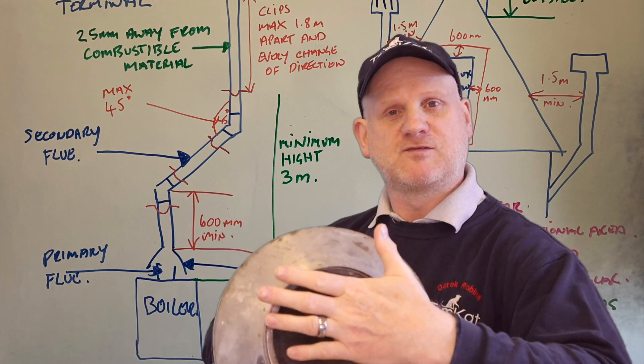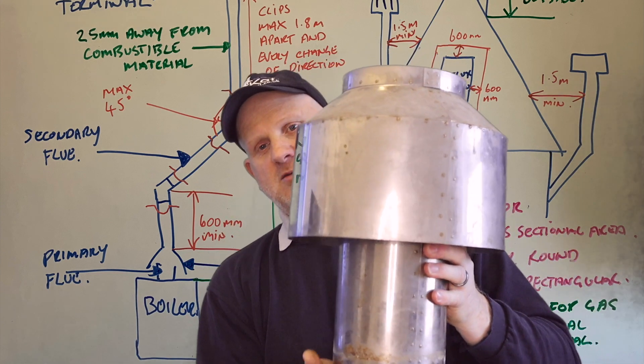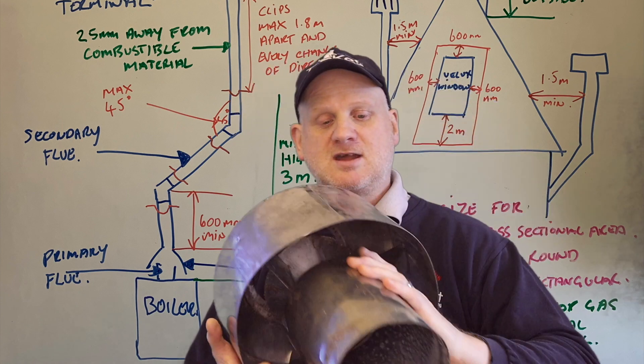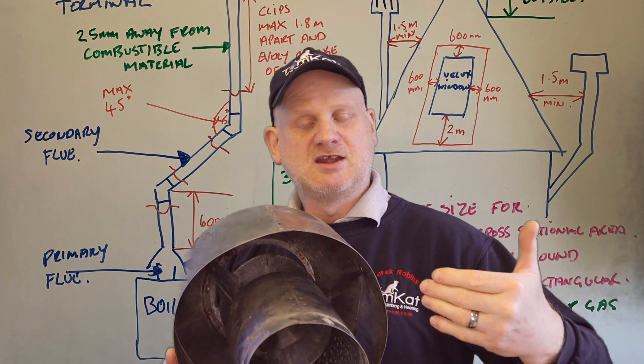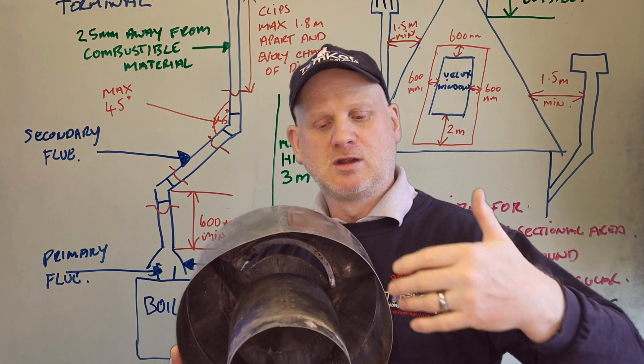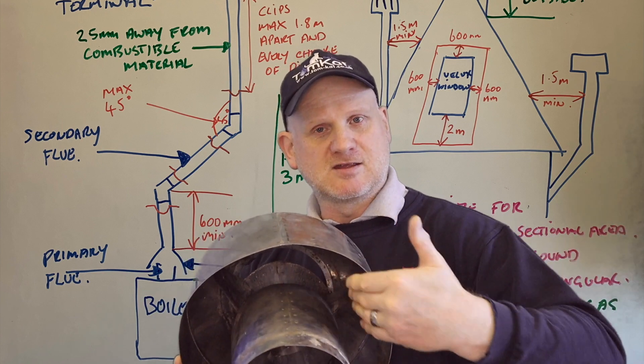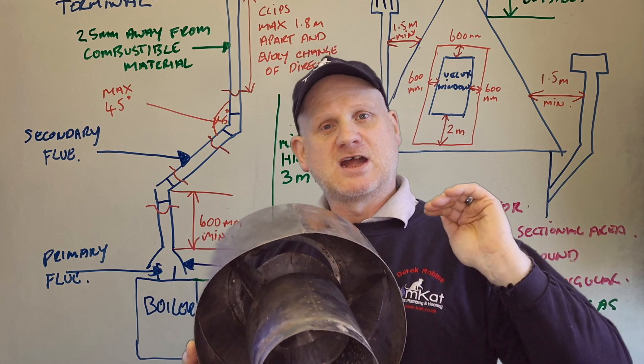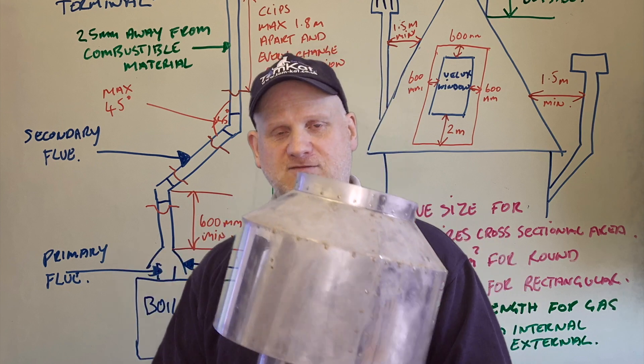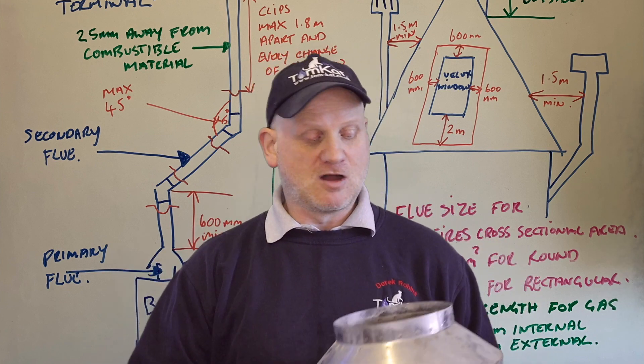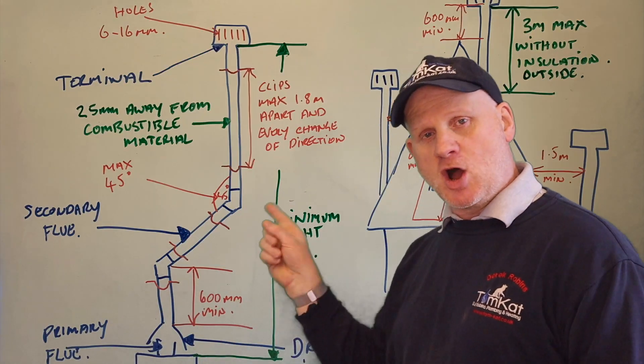On an external draft diverter you can see where the flue connects and the baffle on the inside. This is where we do flue flow tests and spillage checks. If there's excessive pull it's broken here; if air needs to dilute it enters here; and if there's downdraft it exits here. Many draft diverters are built into the appliance.